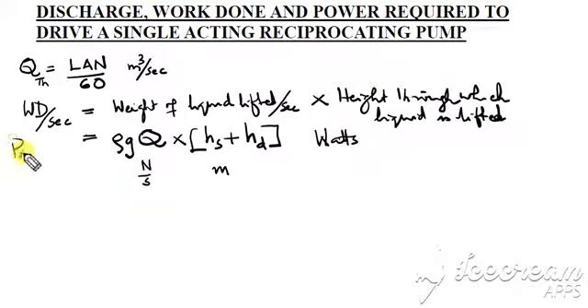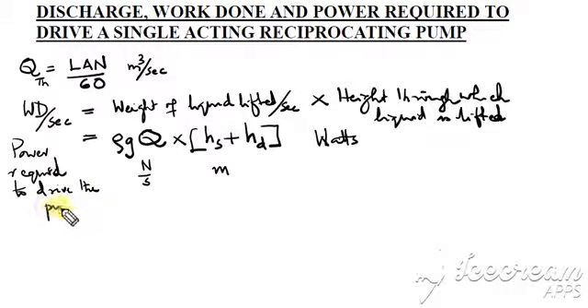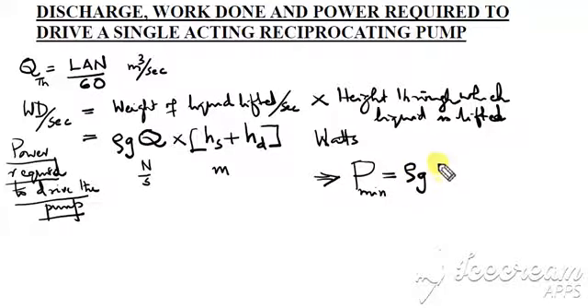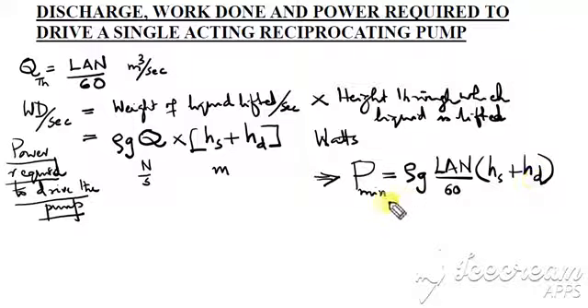This rate of work done is nothing but the power required to drive the pump. Of course, this is the minimum power required to drive a single acting reciprocating pump: P_min = rho × g × Q × (hs + hd). In expanded form, substituting Q = LAn/60, P_min = rho × g × (LAn/60) × (hs + hd). This quantity multiplied by 2 will be the power required to drive a double acting reciprocating pump.